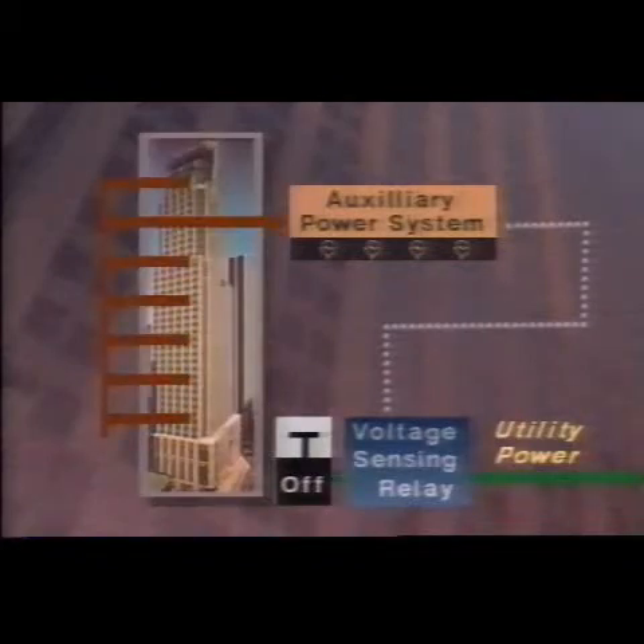Power then flows from the 34th floor auxiliary plant through the building's existing power bus riser to each floor, bypassing the power company's meters. Elapsed time from interruption to auxiliary power takeover, 10 seconds, and it runs without noise, vibration, or other environmental problems to offend building tenants or the surrounding area.